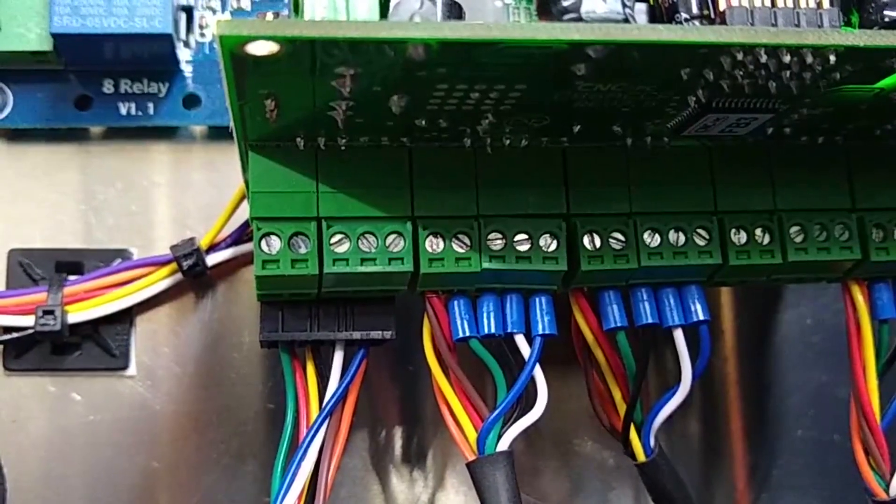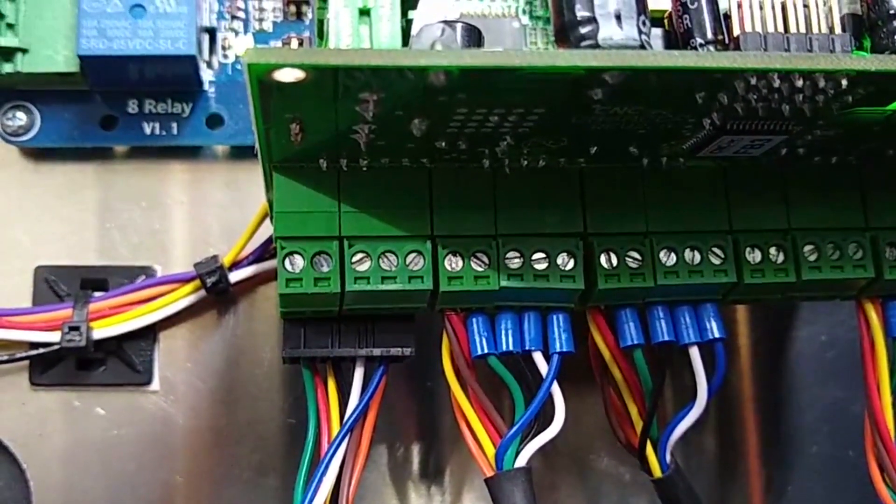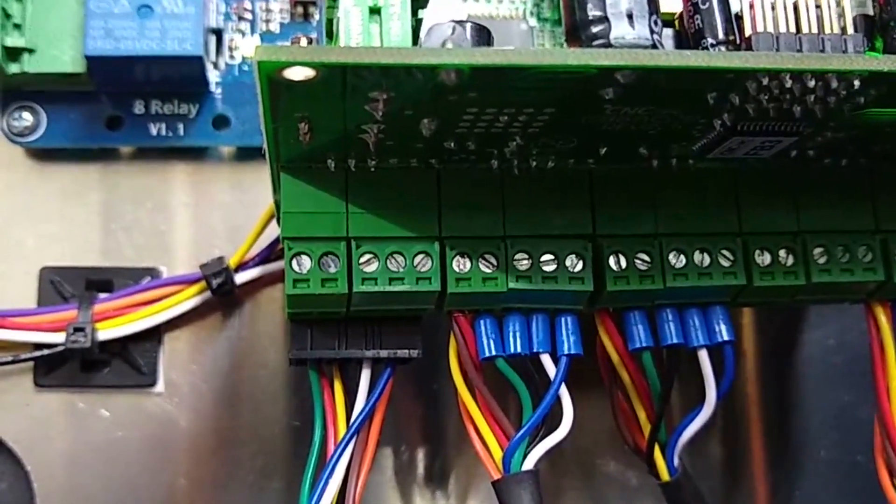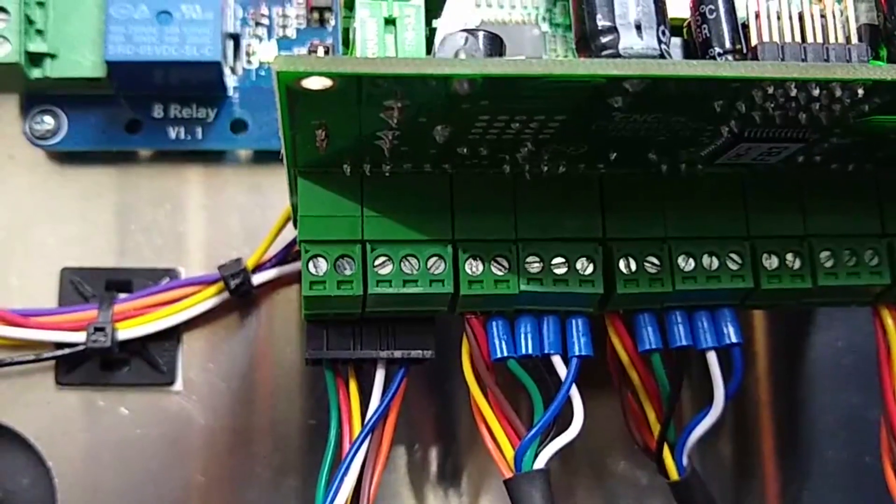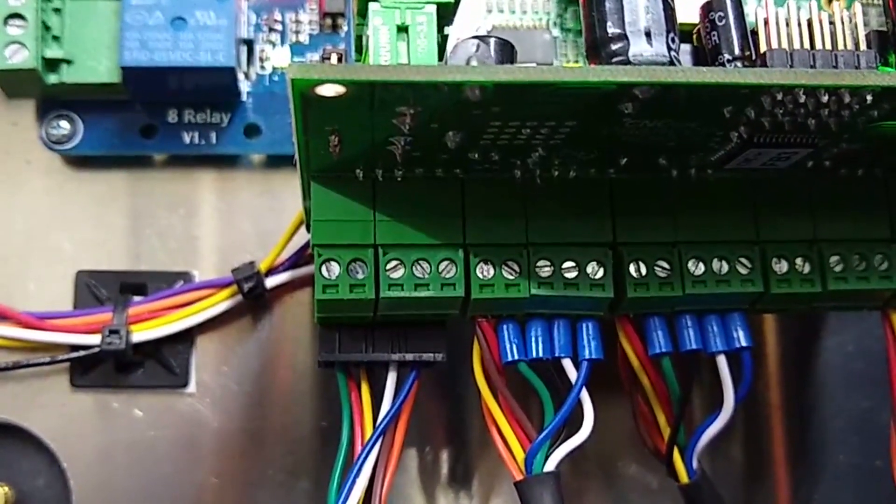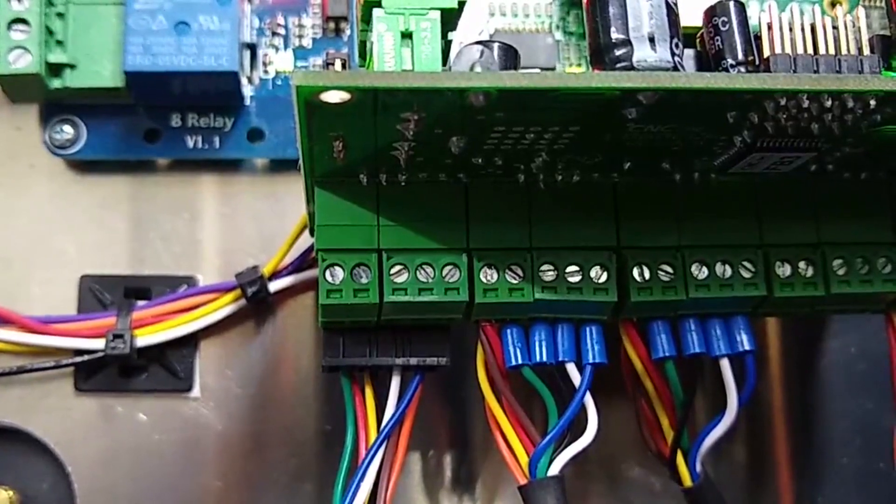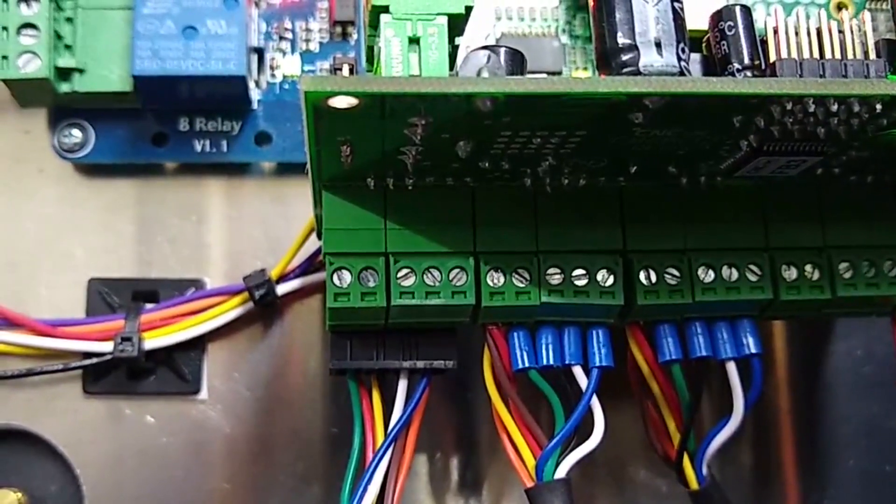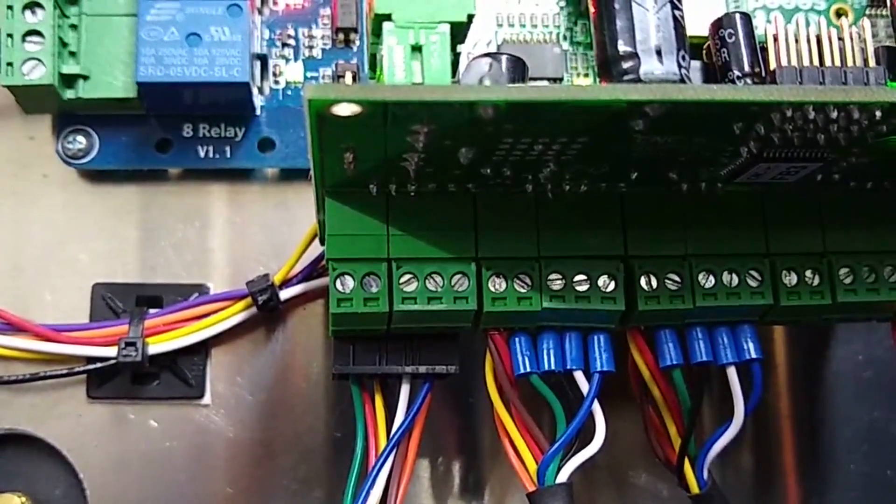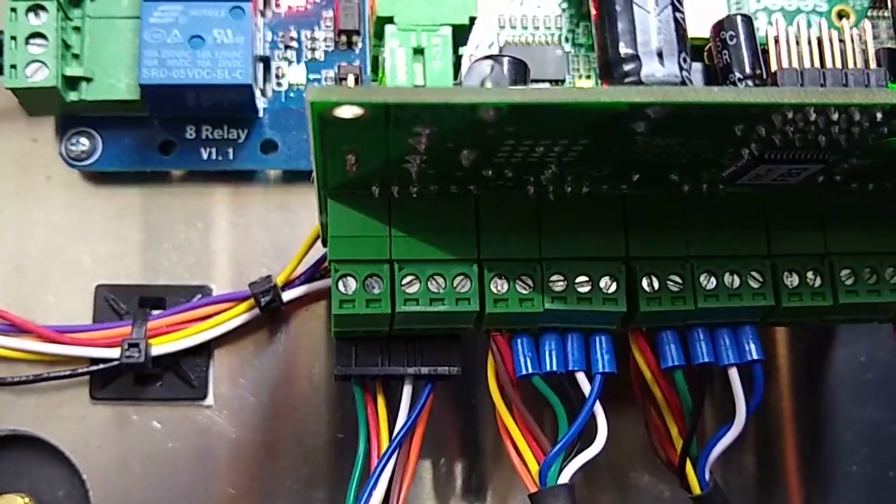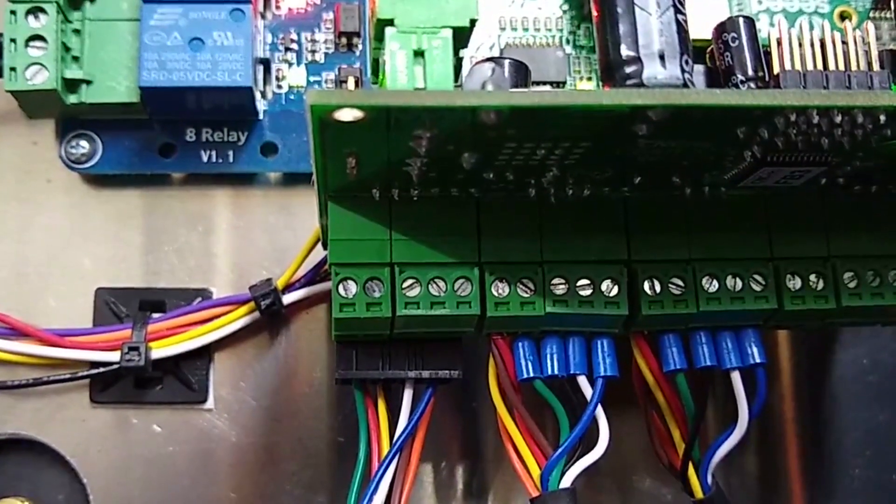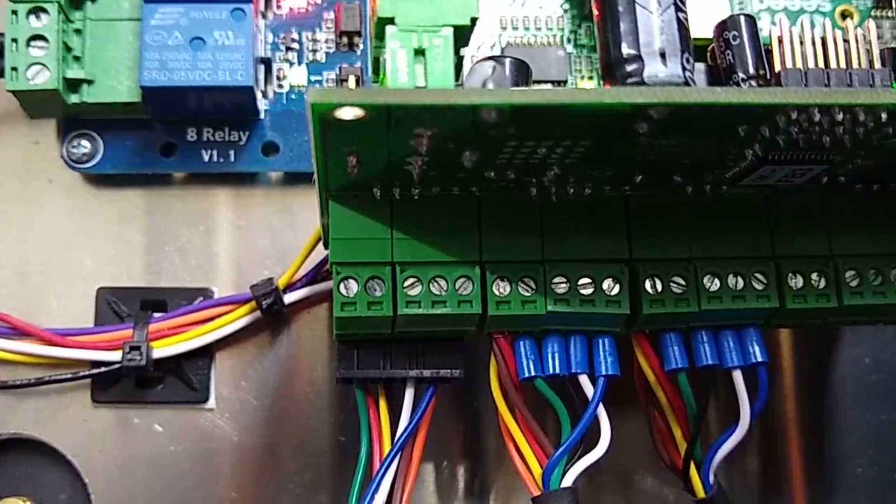Green is the HLFB positive. Black is Input B positive—Input B, by the way, is the step signal. White is Input A, that's the direction signal. And blue is the enable signal.